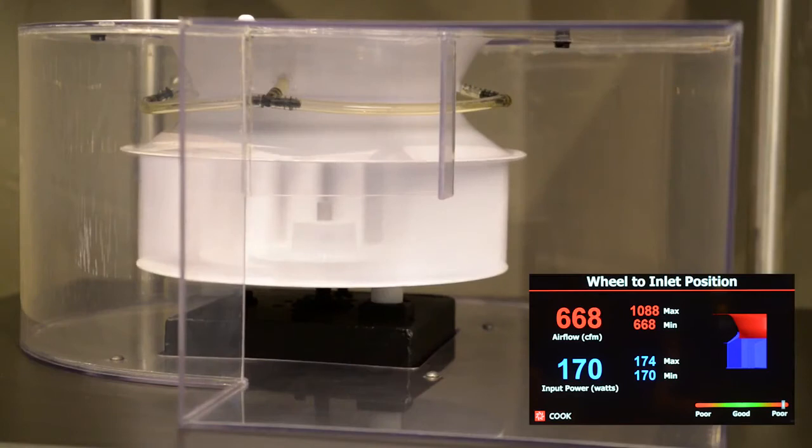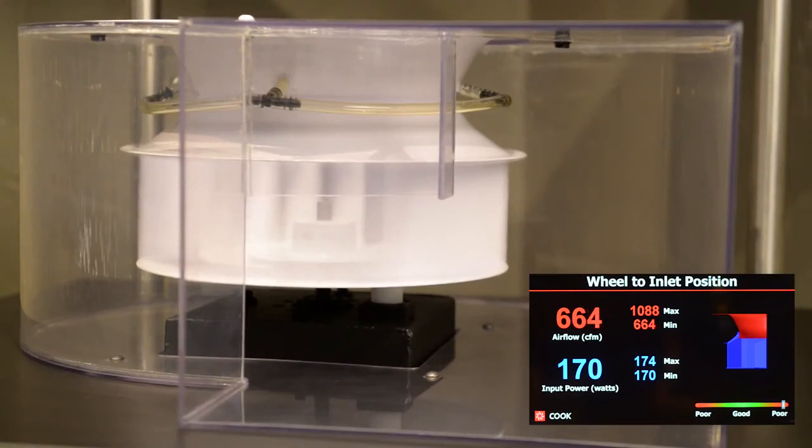As we get to the highest position, let's see what has happened. We've lost nearly 40% of our airflow, but the fan is consuming nearly the same amount of energy.